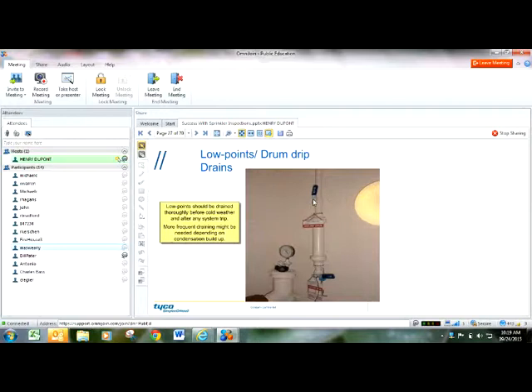So you have a ball valve on top of this drum drip and you have a ball valve on the bottom. What you do to purge these drains is you shut the bottom ball valve, open up the top ball valve, and then any water that's drained on top of there will come down into that barrel. Shut that one, open that one, and purge that water out. You do it over and over and over until you don't get any water out. In the fall months, you want to be doing this on your low point drains every other week probably. And as wintertime gets even closer, you want to step that up a little bit.